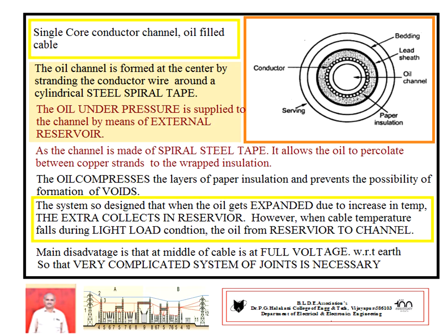See there, this channel is made of spiral steel tape. It allows the oil to percolate between the copper strands to the wrapped insulation. Hence, this oil percolates to the conductor and insulation system, and keeps both the conductor and insulation under pressure.